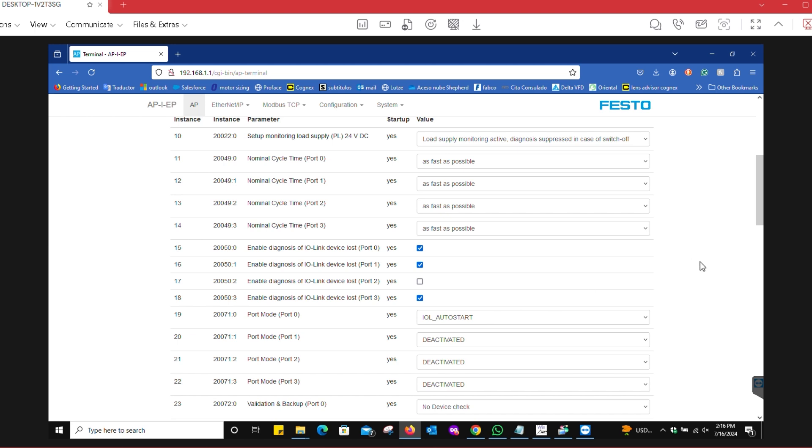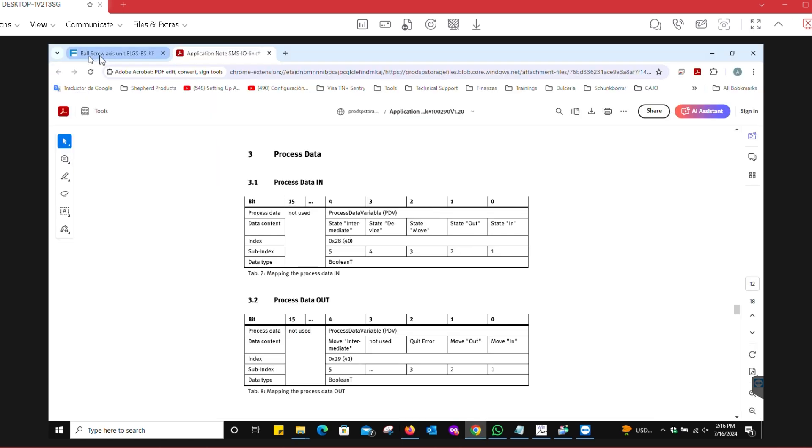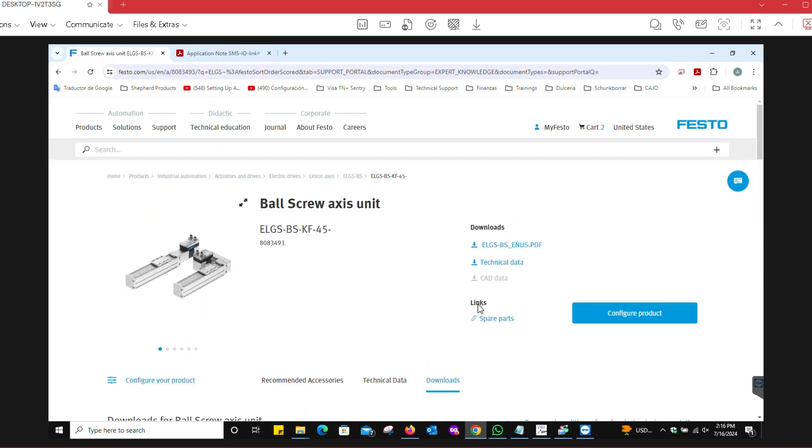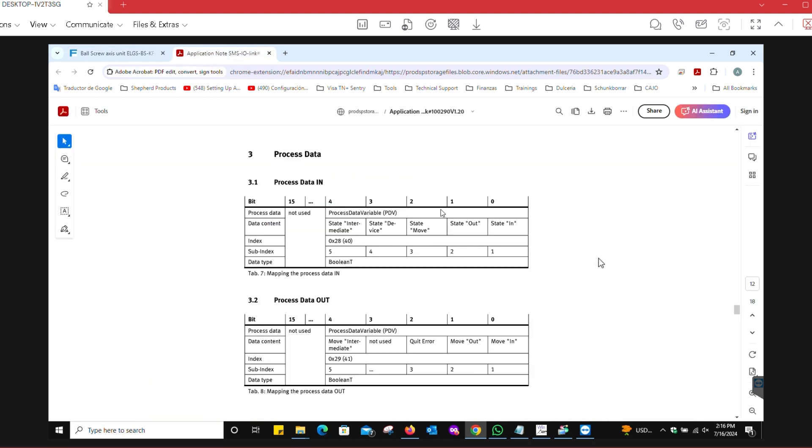The particular device that we're using is an ELGS ball screw. It has a motor attached to it and a linear actuator. This actuator in particular uses two bytes of process data, and you can see it on this little table: two bytes for process data in and two bytes for process data out.